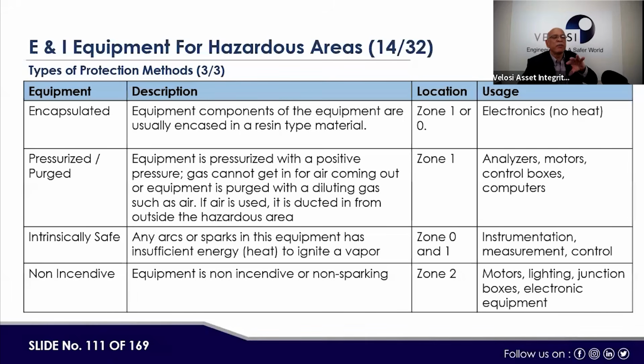Similarly, for encapsulated, the same definition is explained here: the components of the equipment are usually encased in a resin type material. Next is pressurized or purged. This is basically done for a junction box or a control room: the equipment is pressurized with a positive pressure. Gas cannot get in, because there is hydrocarbon outside, but that hydrocarbon should not go inside the junction box or the motor or that particular equipment. The equipment is pressurized with a positive pressure so gas cannot get in, or the equipment is purged with a diluting gas such as air. If air is used, it is ducted in from outside of the hazardous area. So for analyzers, motors, control boxes, and computers, these kinds of arrangements are made.